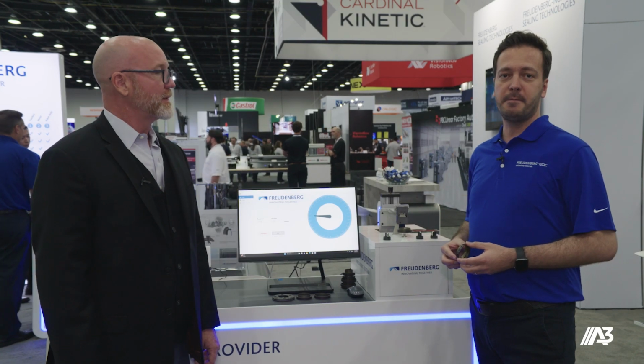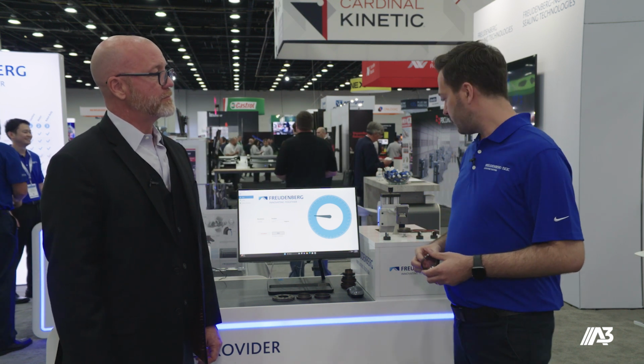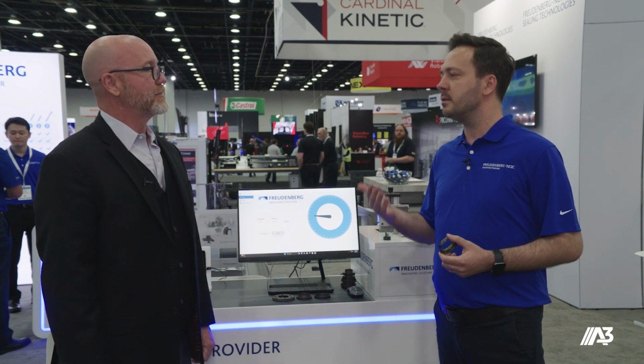So what are the benefits of the magnetic encoder, say, over the optical encoders? Yeah, there are a couple of benefits. First of all, they are smaller than the traditional encoders, so downsizing is one of the benefits. And second, optical encoders are really sensitive to the environment, but magnetic encoders are resistant to high temperature, high speeds, humidity, and difficult working conditions, which contain oil, dust, dirt, etc. The signals are not affected by the environment easily. So this is the biggest benefit of the magnetic encoders.